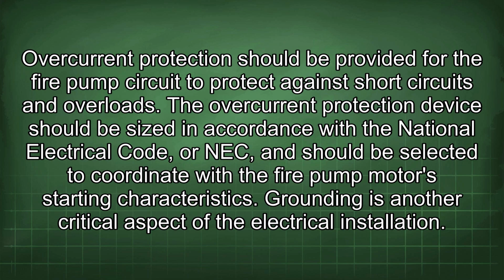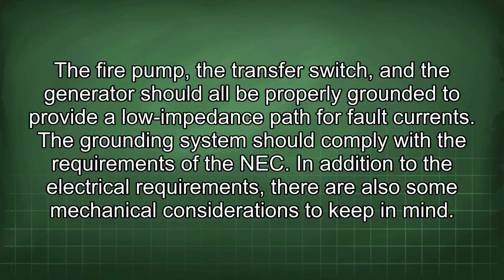Overcurrent protection should be provided for the fire pump circuit to protect against short circuits and overloads. The overcurrent protection device should be sized in accordance with the National Electrical Code, or NEC, and should be selected to coordinate with the fire pump motor's starting characteristics. Grounding is another critical aspect of the electrical installation. The fire pump, the transfer switch, and the generator should all be properly grounded to provide a low impedance path for fault currents. The grounding system should comply with the requirements of the NEC.